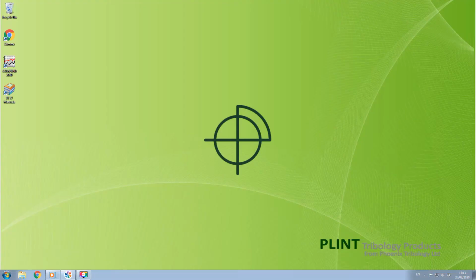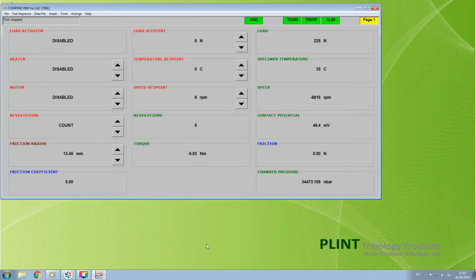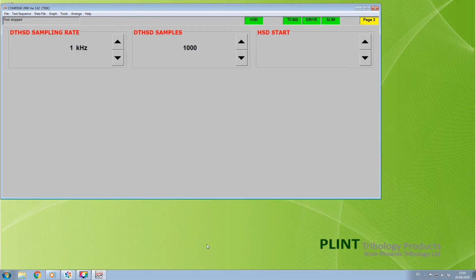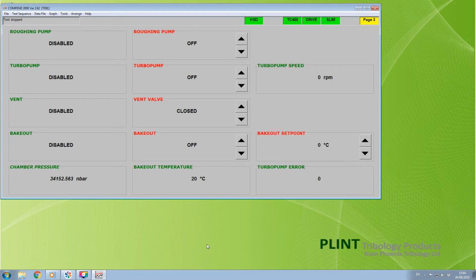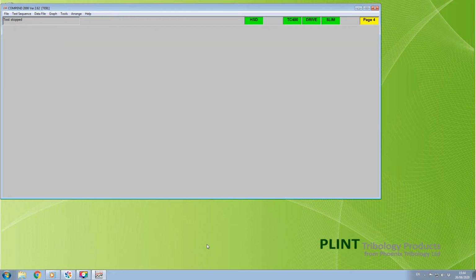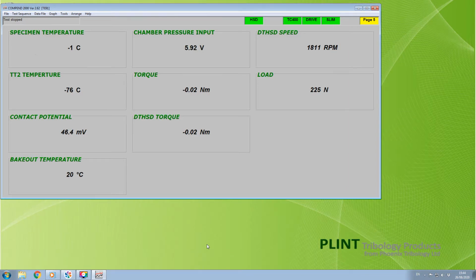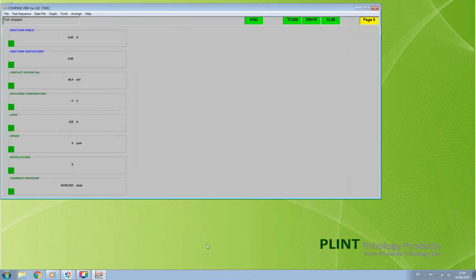Double-clicking the Compend icon on the Windows screen launches the software at page 1, the primary user interface screen. A single screen or page contains up to 40 boxes, and there are a total of 6 pages. Page 2 is for manual control of the high-speed data acquisition channels. Pages 3 and 4 are available for controlling additional peripheral devices if required and for additional sensors and derived channels. Page 5 is used for calibration. Page 6 duplicates boxes from page 1 and is used to define the order of columns in data files. It may also contain machine status information that can be used for fault finding.